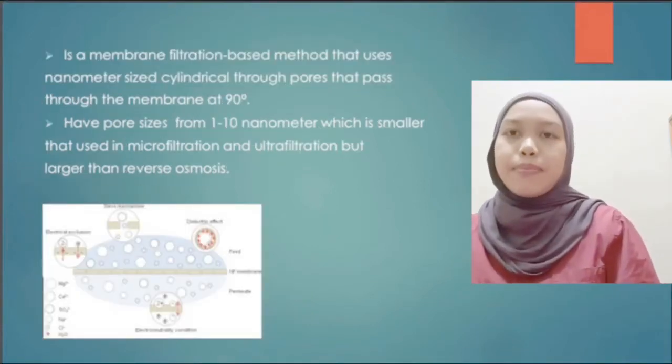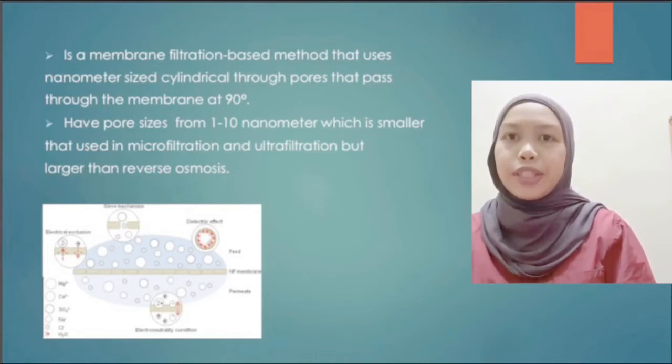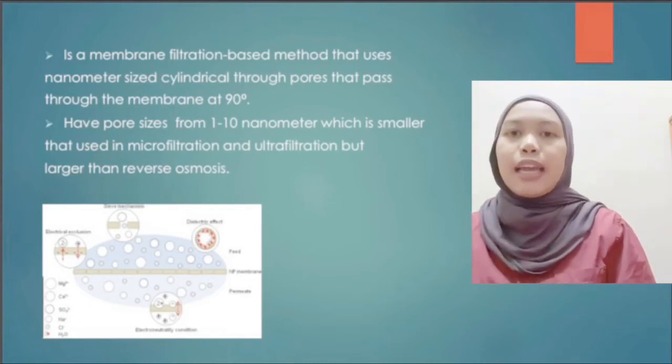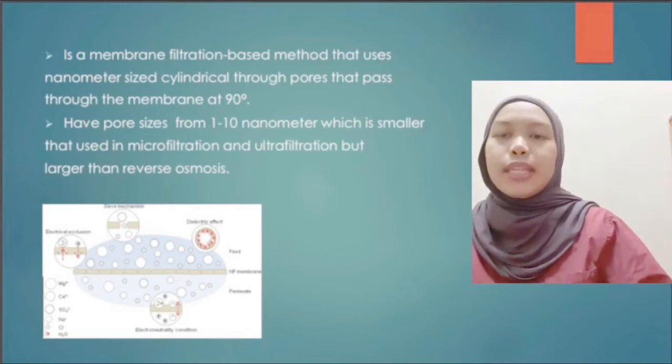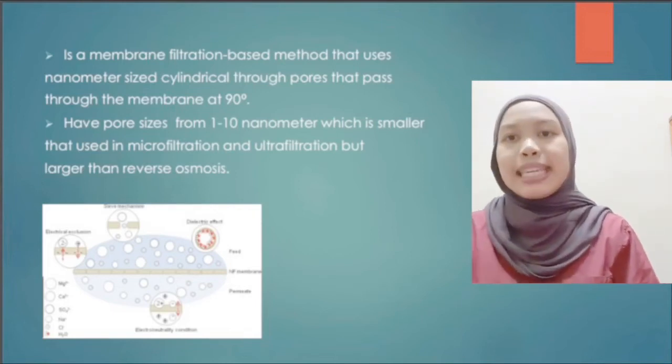Nanofiltration is a membrane filtration-based method that uses nanometer-sized through pores that pass through the membrane at 90 degrees. It has a pore size from 1 to 10 nanometers, which is smaller than that used in microfiltration and ultrafiltration, but just larger than reverse osmosis.